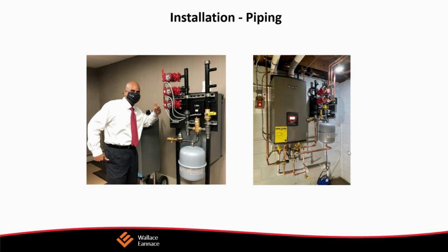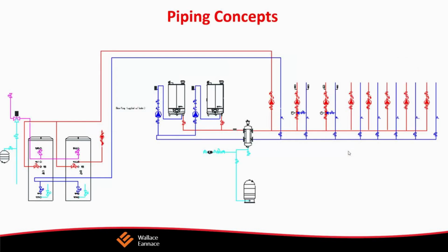The way to solve that problem, to get equal flow through the radiators, is to do a 2-pipe reverse return system. It uses more pipe. It's a little more expensive. It is easy to zone. It will balance out the delta T, and very importantly, the radiators will all get equal flow. The secret to a 2-pipe reverse return system, as you can see, this is the first one in, and it's the last one back. It's very simple. First one in, last one back. Last one in, first one back. That's how you do a 2-pipe reverse return system.